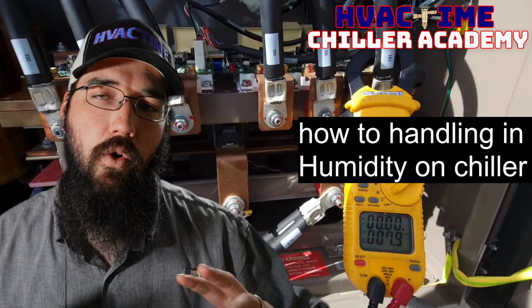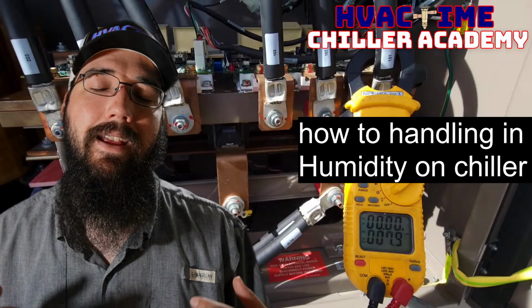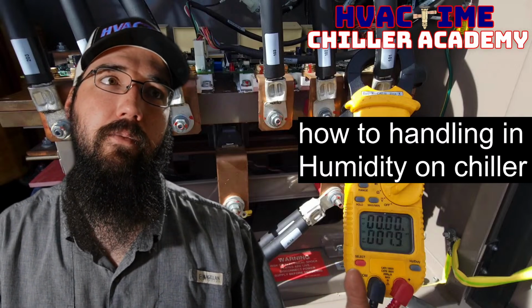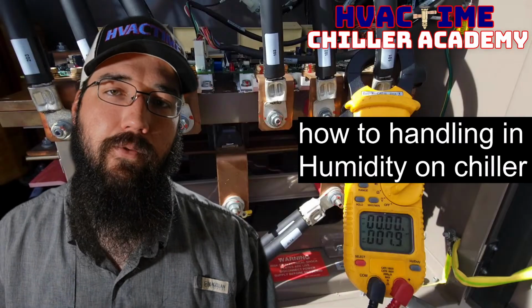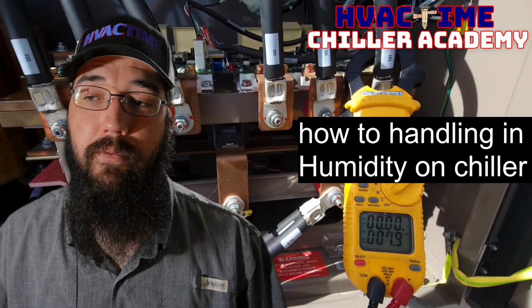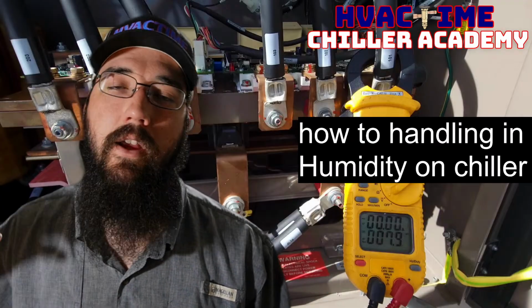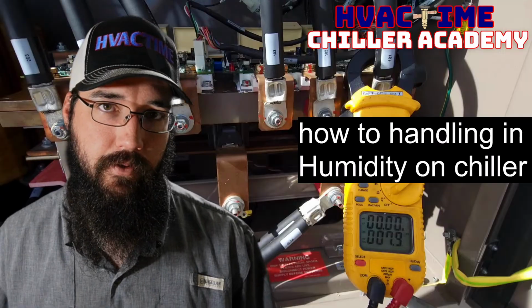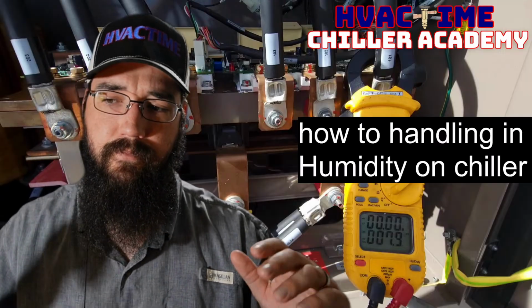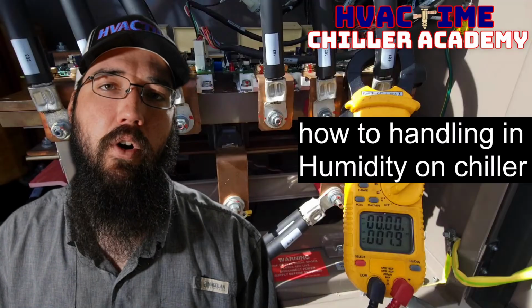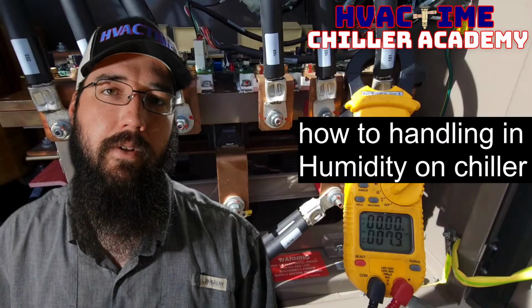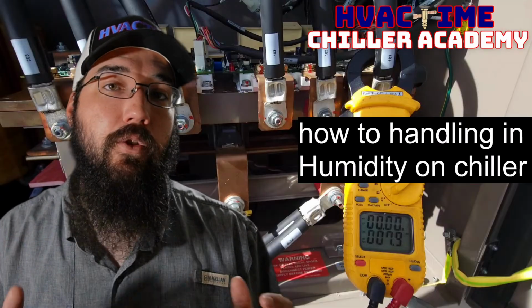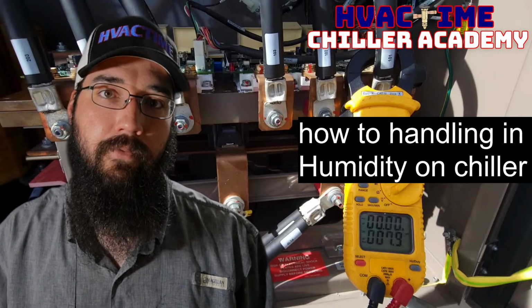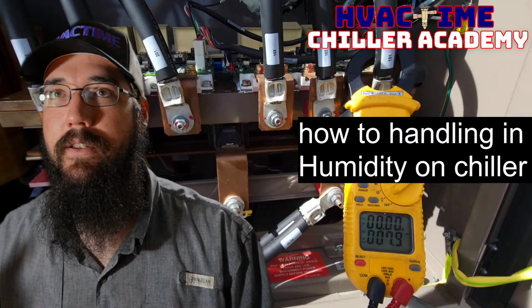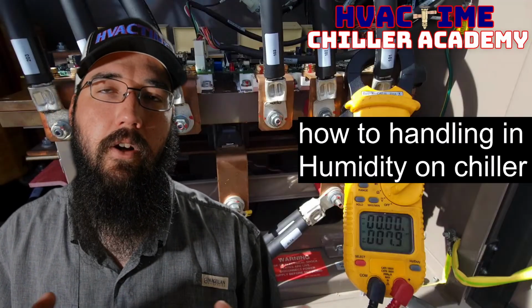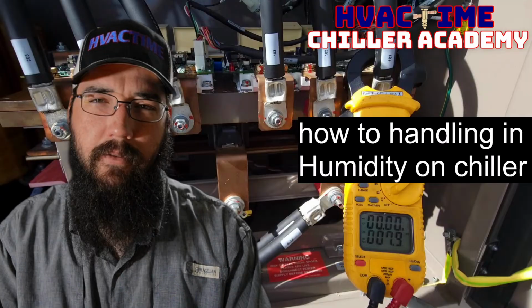So the whole purpose of those mid 40s is so that we can achieve a cold enough coil to allow for proper latent heat intake. These are the same reasons why we run in the mid to low 40s with RTUs and split systems and everything else in our trade that operates within that saturation band. That is the purpose we're trying to achieve. It is about humidity control. Now, you could go either way. Let's just focus on comfort here, because we could get into data centers and how they control, and all of this will play a part. So yeah, we can run with this.